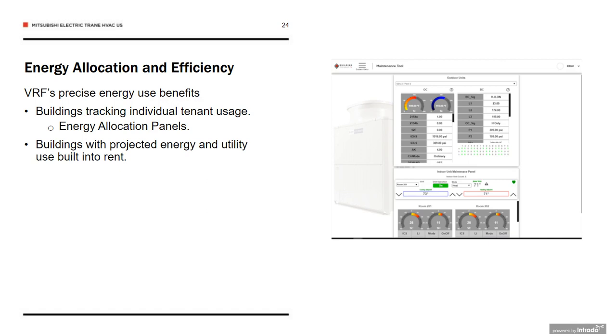So at this point, we understand that VRF is a precise energy use system. It uses inverter technology to deliver exactly and precisely what you need. From the fact that we can see how the system is constantly running and always communicating, we can pull out information such as energy allocation to maximize the efficiency of the system. If you're building a development and you have multiple tenants, you would be able to add some additional software and hardware to the VRF system to generate projected energy usage as well as utility apportionment for each tenant within that building to bill out for the rent. And so VRF would allow you to create a bill to send to that tenant that you could easily leverage for better performance and to create a bill for that end user.